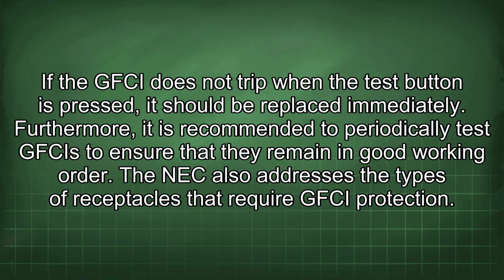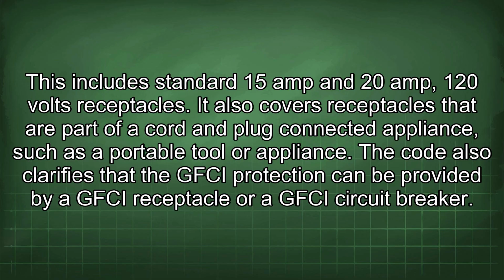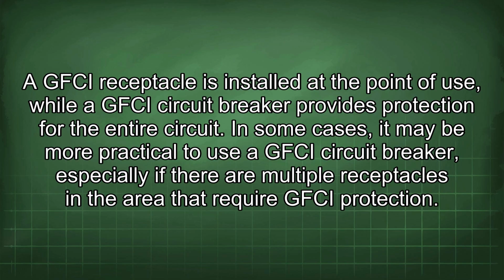The NEC also addresses the types of receptacles that require GFCI protection. This includes standard 15 amp and 20 amp 120 volt receptacles. It also covers receptacles that are part of a cord and plug connected appliance, such as a portable tool or appliance. The code also clarifies that the GFCI protection can be provided by a GFCI receptacle or a GFCI circuit breaker. A GFCI receptacle is installed at the point of use, while a GFCI circuit breaker provides protection for the entire circuit. In some cases, it may be more practical to use a GFCI circuit breaker, especially if there are multiple receptacles in the area that require GFCI protection.